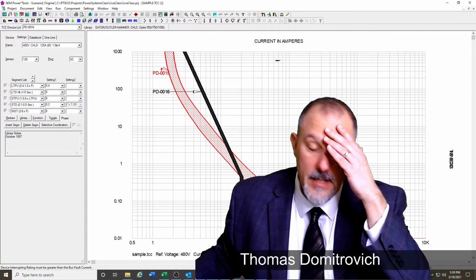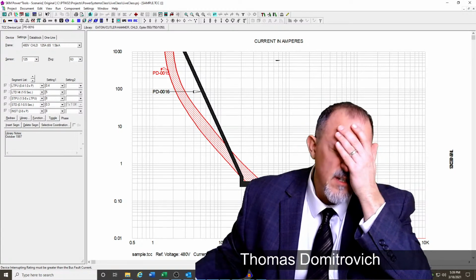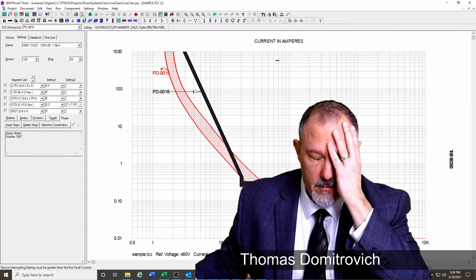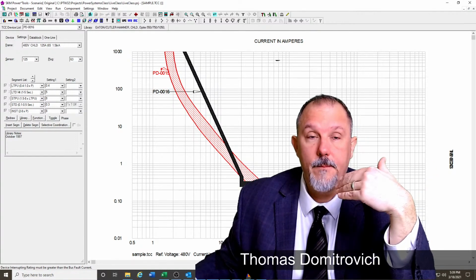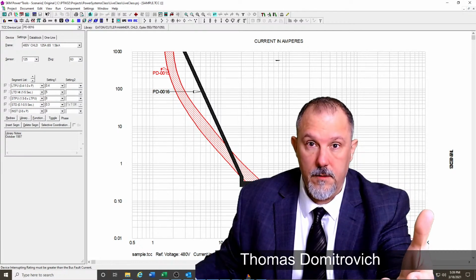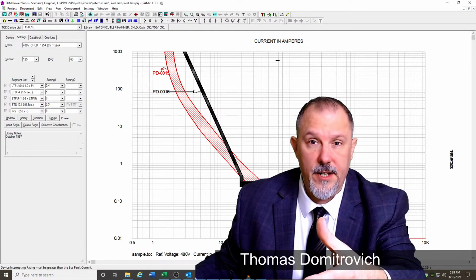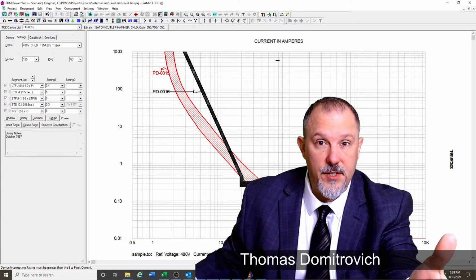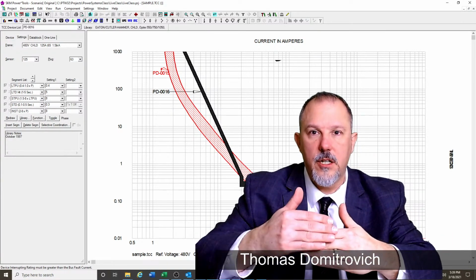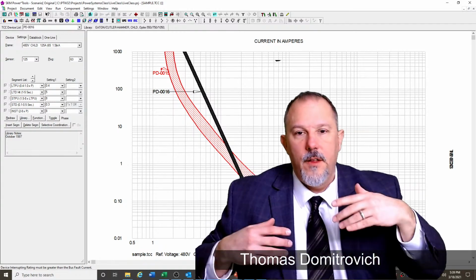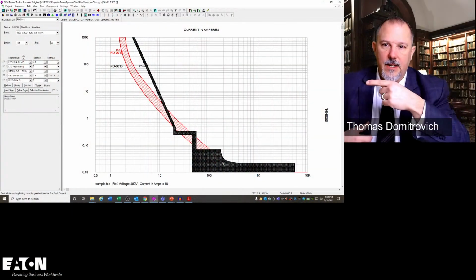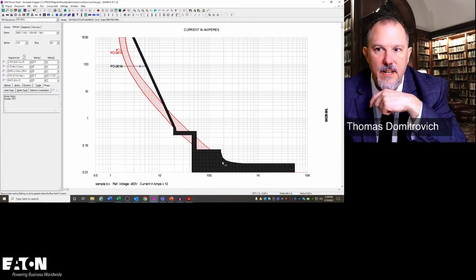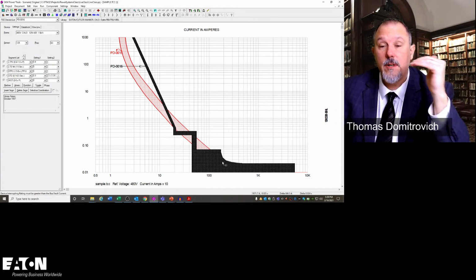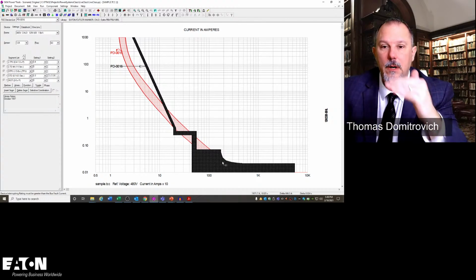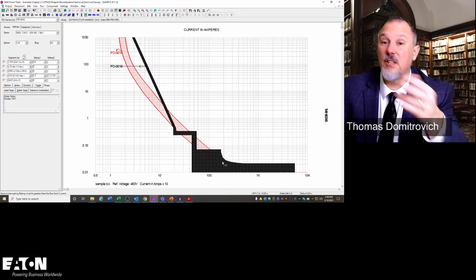All right, let me explain something here too. So these trip curves, I'm an engineer. I'm an electrical engineer. Conservative. Engineers have to be conservative. What do I mean by that? I would rather have you overdressed for an arc flash event than underdressed. So I may estimate things to put the numbers a little higher. The engineers on products, like for this curve, that fat band that's 0.07 seconds, that tells you that it's going to trip somewhere between 0 seconds and 0.07 seconds. The reality of the fact is it's probably going to go a lot faster.